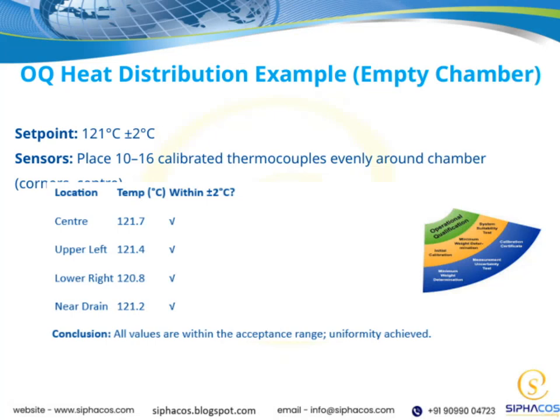Now, let's take a closer look at this OQ heat distribution example within an empty chamber. The set point we're aiming for is 121 degrees Celsius, with a tolerance of plus or minus 2 degrees. This ensures we maintain consistent and accurate temperature control.